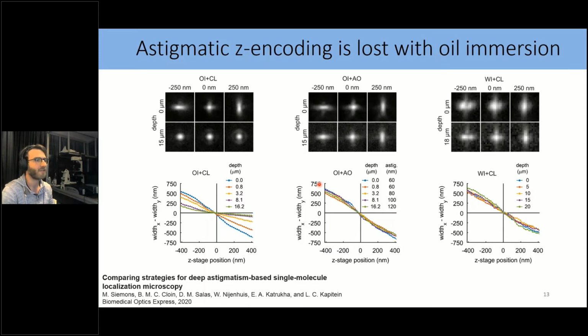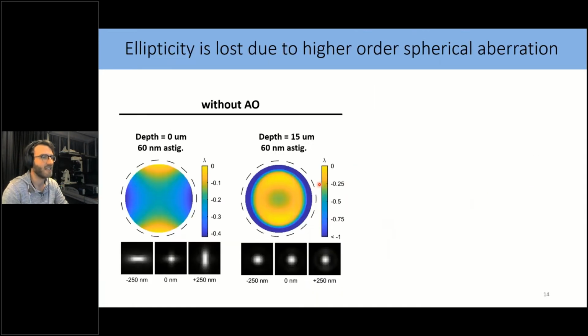To investigate it further, or at least try to see if we indeed are correct, I performed some modeling of this. So these two plots indicate the phase of the pupil at the cover slip and at a depth of about 15 microns into the sample. As you can see, at the cover slip we have a very nice point spread function where the ellipticity is clearly visible, and it's no longer the case when we image at 15 micron depth.